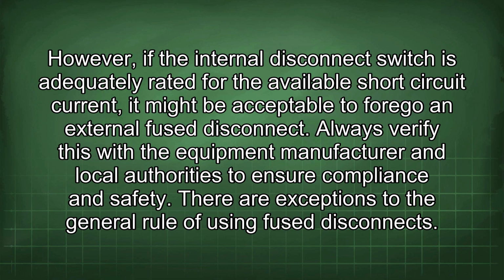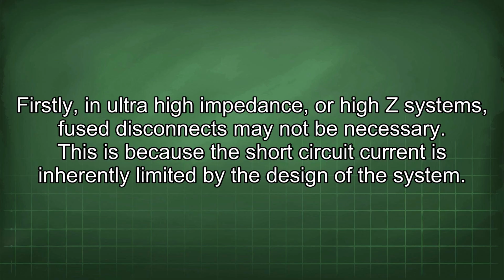However, if the internal disconnect switch is adequately rated for the available short-circuit current, it might be acceptable to forego an external fused disconnect. Always verify this with the equipment manufacturer and local authorities to ensure compliance and safety. There are exceptions to the general rule of using fused disconnects. Firstly, in ultra-high impedance or high-Z systems, fused disconnects may not be necessary. This is because the short-circuit current is inherently limited by the design of the system.